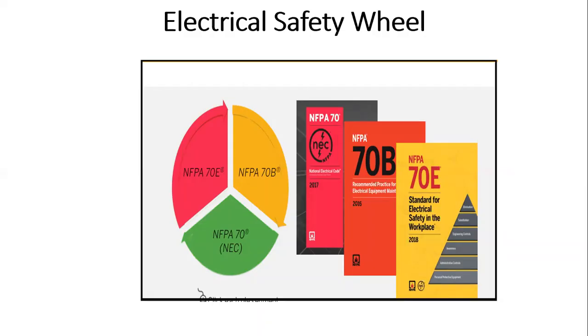NFPA 70B is related to the maintenance of electrical equipment. It says that periodic maintenance, condition-based maintenance, or risk-based maintenance should be carried out on your electrical equipment to identify any impending failure using thermography or ultrasound discharge detection, so you may find a problem arising and take preventive, emergency, or condition-based maintenance to keep the integrity and safety of the equipment.